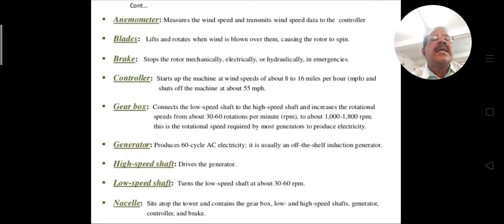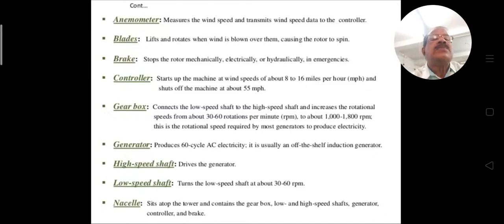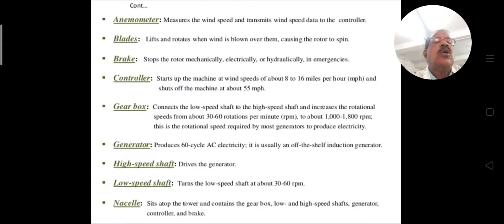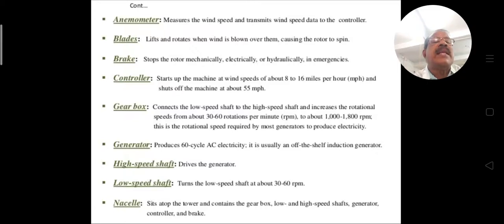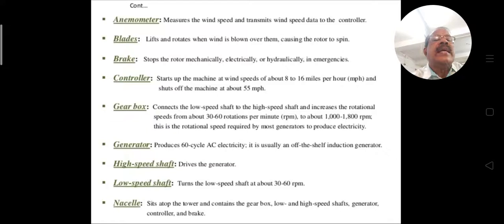The gearbox connects the low speed shaft to the high speed shaft and increases the rotational speed from about 30 to 60 rotations per minute up to about 1,000 to 1,800 RPM — the rotational speed required by most generators to produce electricity. The gearbox maintains this certain speed.